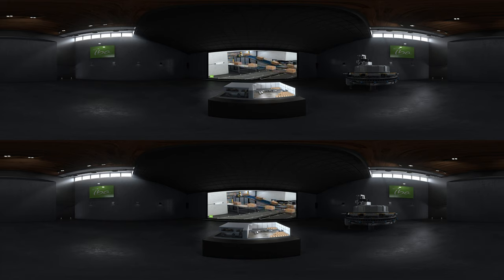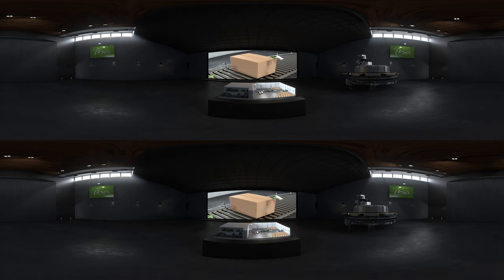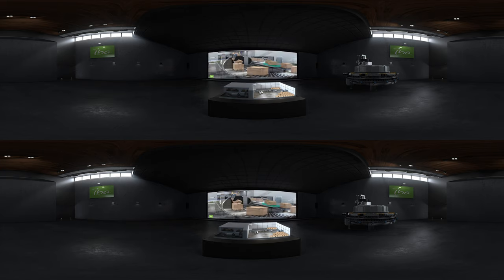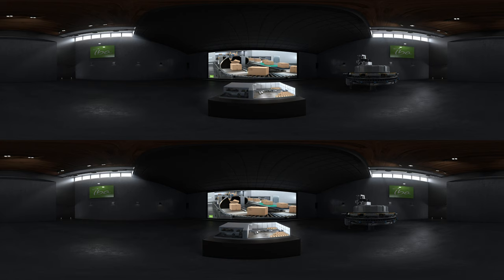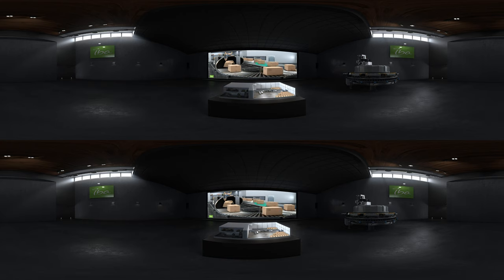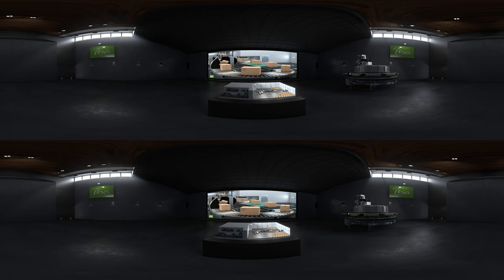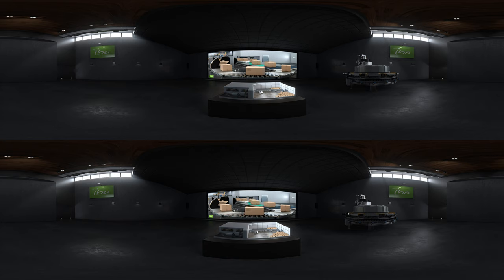If the treatment is completed, the boxes are directed to the unloading station. The dosimeters are then analyzed in the dosimetry room to validate the treatment by measuring the dose received by the product on its surface. In case they need a second side irradiation, the boxes remain on the conveyor, pass through a flipping machine that rotates them, and are re-injected in the main loop to be irradiated a second time.